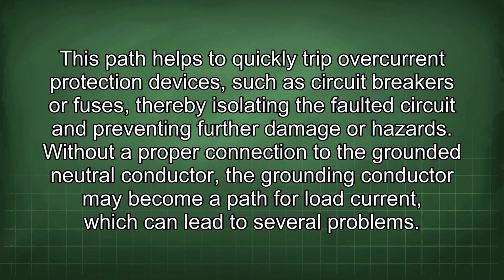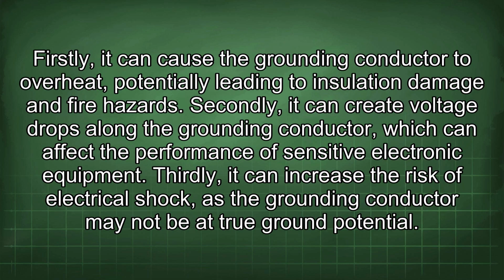Without a proper connection to the grounded neutral conductor, the grounding conductor may become a path for load current, which can lead to several problems. Firstly, it can cause the grounding conductor to overheat, potentially leading to insulation damage and fire hazards. Secondly, it can create voltage drops along the grounding conductor, which can affect the performance of sensitive electronic equipment. Thirdly, it can increase the risk of electrical shock, as the grounding conductor may not be at true ground potential.